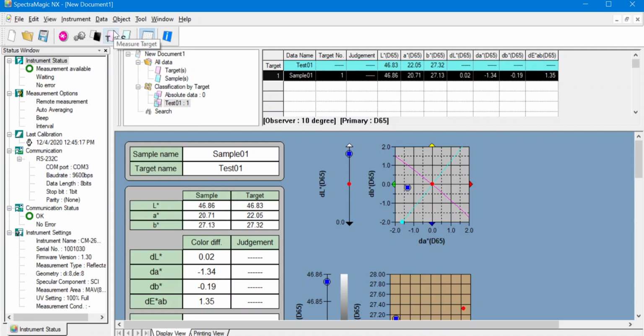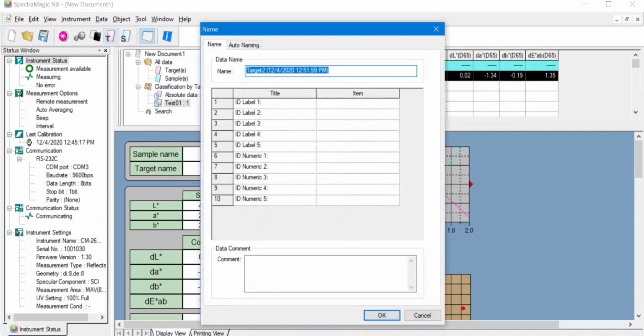So let's measure another target. I will click the word target again, and again it defaults to the date and time. I would measure a white sample over here. So I would put this target as test 02, and when I click OK, it will immediately take measurements. Please ensure that before you select the word target, you have already placed your equipment on the target color.